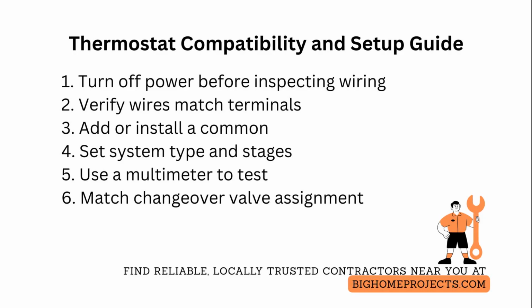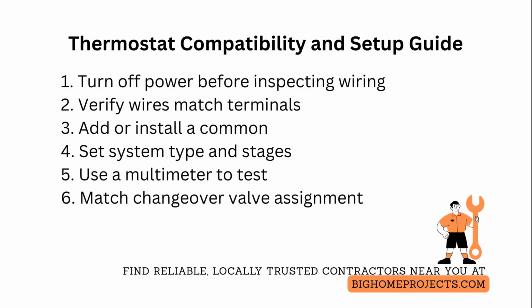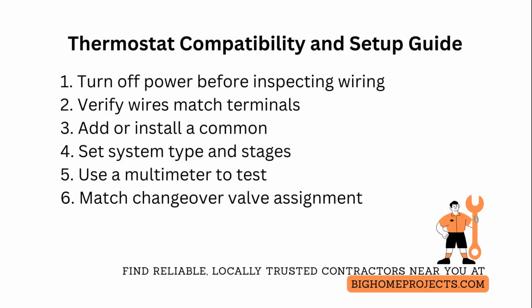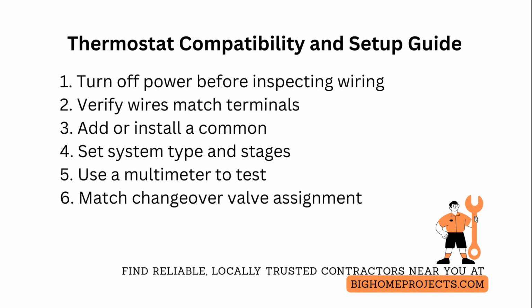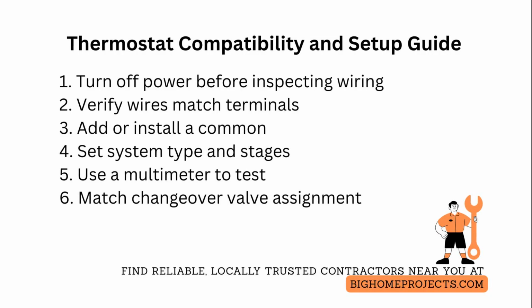For heat pump systems, ensure the changeover valve lead, often labeled O or B, is assigned correctly and that the thermostat's changeover is matched to the outdoor unit's manufacturer preference, so reversing valve operation is not reversed. When adaptive features such as two-stage compressor control or demand response are missing, verify the thermostat model actually supports those features and that feature toggles in advanced setup are enabled. If not supported, replace with a model that explicitly lists those capabilities.